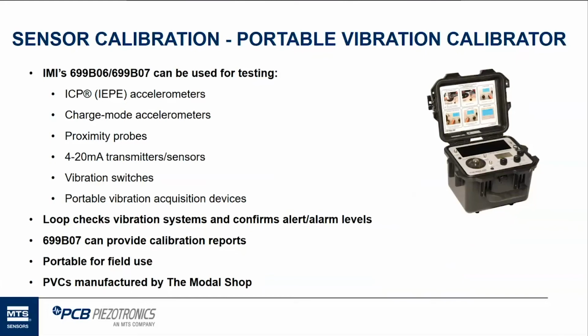Our higher-end version, the 699B07, can provide calibration reports. If any companies require that the sensors have a calibration report on file after calibration, because a lot of companies will just send out their sensors to get calibrated by a company, they'll get a report back and file that away. Sometimes that's required. So our higher-end unit, the 699B07, or the Modal Shop version 9110D, which is the exact same unit, it's just their model number, can provide calibration reports out of the unit itself.